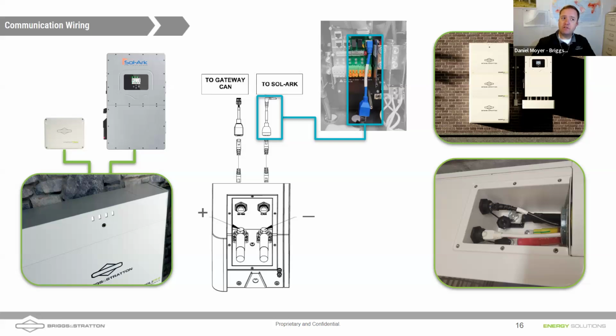I don't believe so. I guess technically you could. One could be serving as your utility connection. The other could be serving as your generator, but you would only be able to use one set of 2-wire starts. Right. And so if you had a manual start generator on your grid port that represented your grid, I guess, for an off-grid system, you could do that.